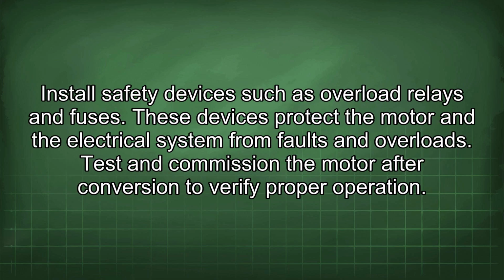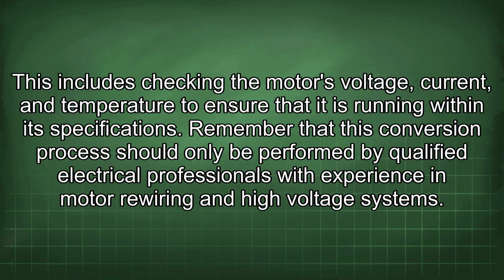Install safety devices such as overload relays and fuses. These devices protect the motor and the electrical system from faults and overloads. Test and commission the motor after conversion to verify proper operation. This includes checking the motor's voltage, current, and temperature to ensure that it is running within its specifications.